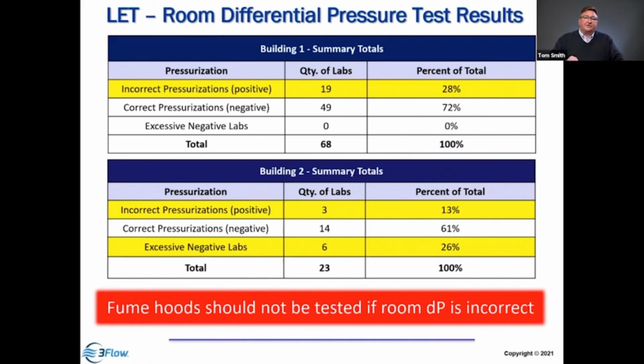So the fume hood should not really be tested until it's confirmed that the pressurization of the space is correct. If you test the hood now and the space is not correct, you're saying, yes, it may or may not be working under this set of prevailing conditions, but if those prevailing conditions are incorrect or improper, then you may be giving a false sense of safety. So it's important that the lab and the hood are operating properly in order for you to put that sticker on the hood saying it's certified.